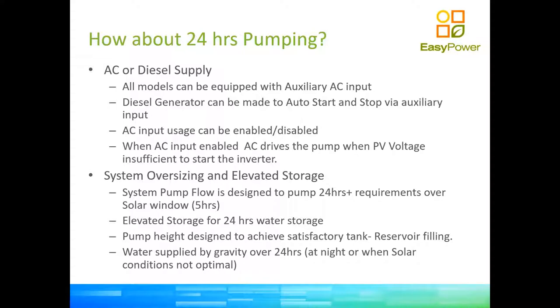Another alternative is to use this equipment during load shedding, since it will pump even without AC. For 24-hour pumping applications, you can have an AC feed or a diesel generator connected to the pump inverter. If all fails, you still have the possibility of pumping five hours a day directly from the sun. The pump inverter will not see a difference between a generator and the grid, and it comes with a dry contact that can be used to actually start a diesel generator remotely.